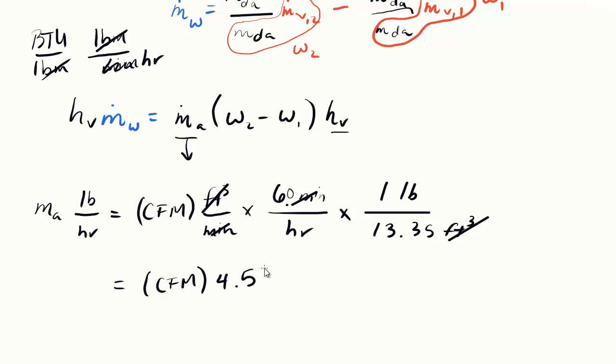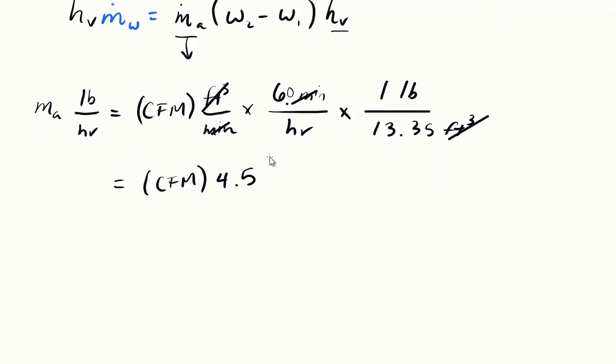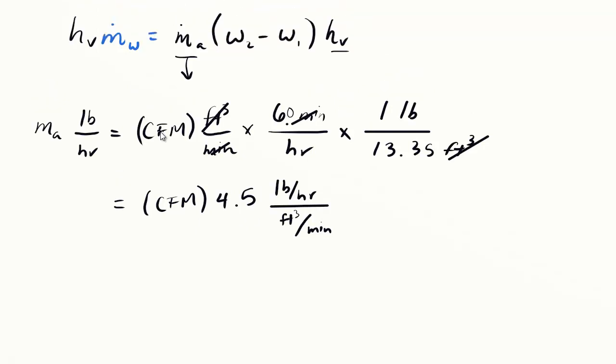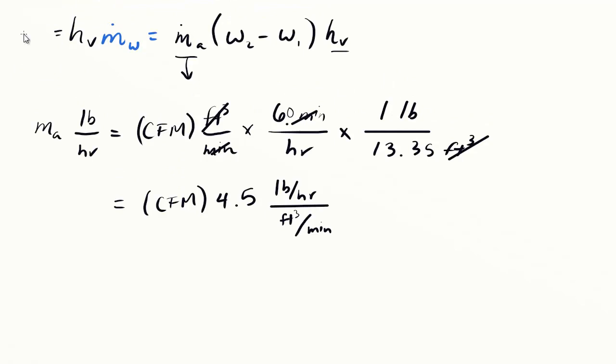The units on this 4.5 are pounds per hour per CFM, though we'll often leave this out in shorthand formulas. The CFM value you put in is in feet cubed per minute, and what you get back is pounds per hour. We can replace the mass flow rate of air with this expression. This is equivalent to our latent load. Q latent in BTU per hour equals 4.5 multiplied by CFM multiplied by delta omega multiplied by the latent heat of vaporization.